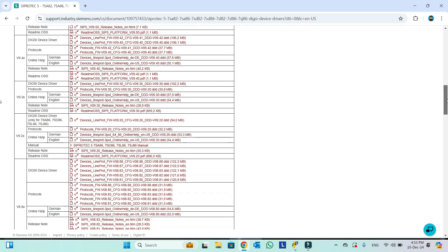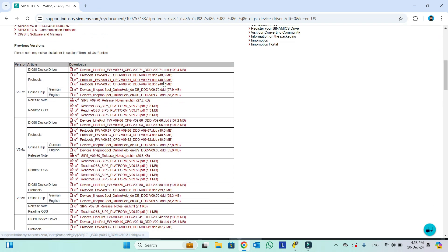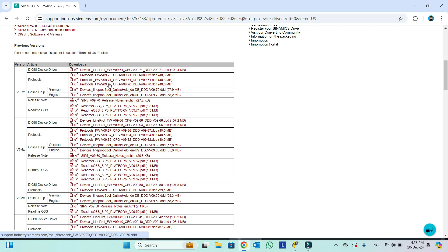For example, this 9.7 we have device driver, this we need, and we have protocol, this we need. In protocol, we have different versions. If we want to download online help, we can download in German and English language. This is the release note and this is the readme. But the most important things out of this is the device drivers and protocol. These two are necessary to communicate with the relay.